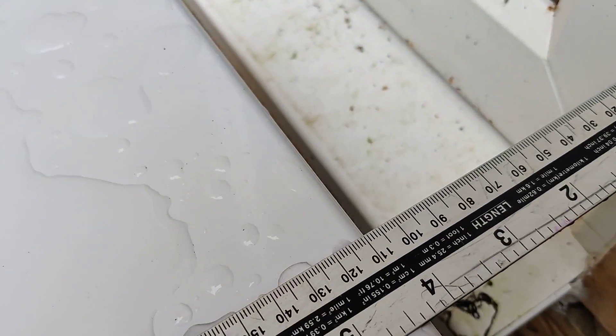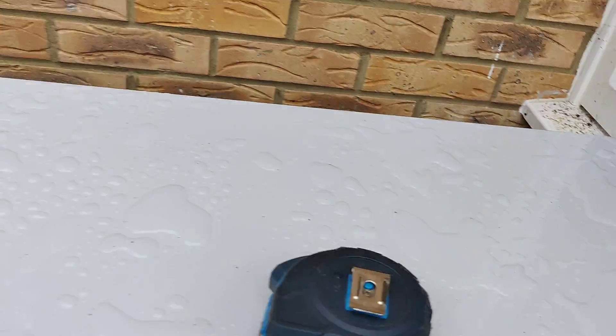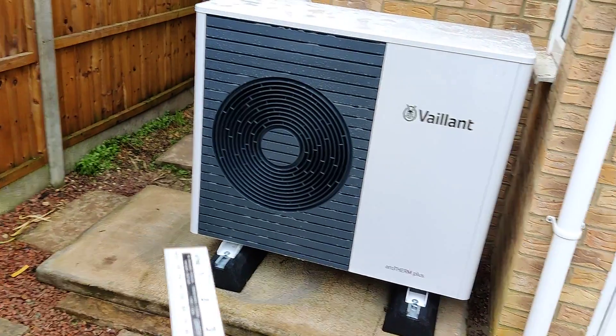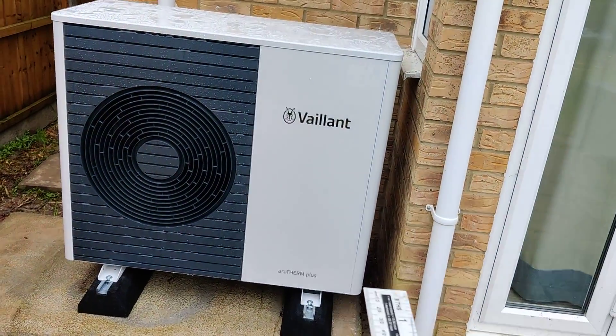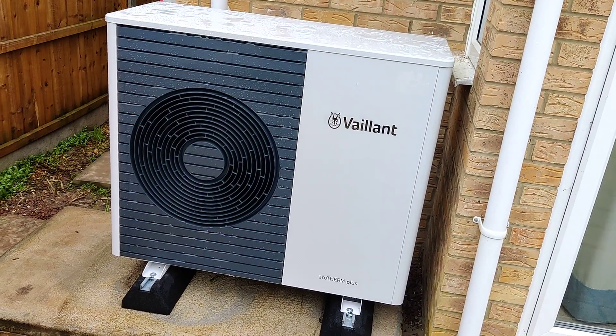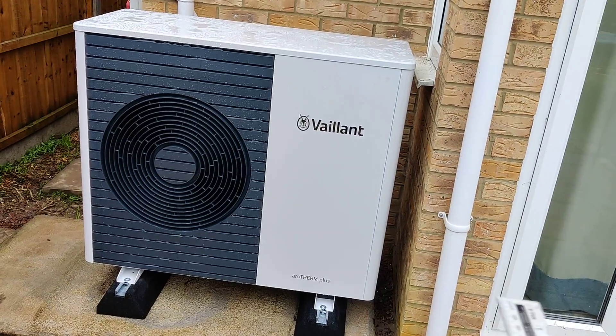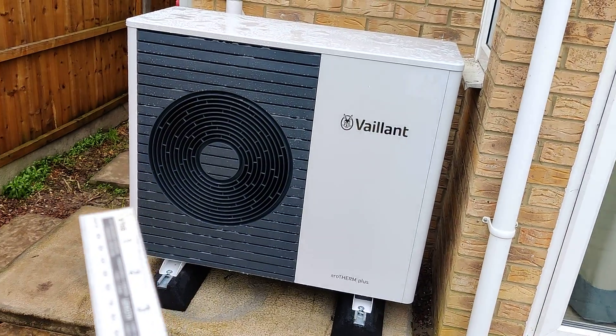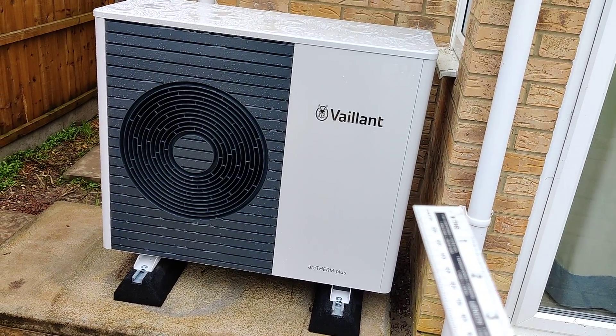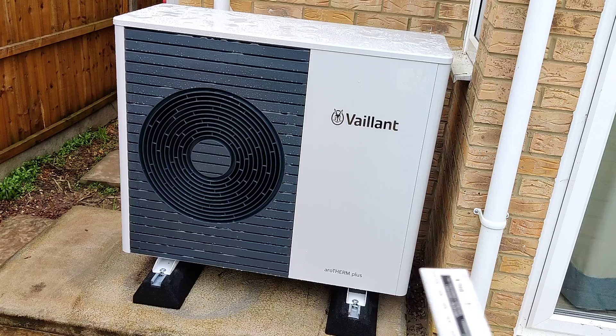Over this side where people said we didn't have clearance — we've got 110mm. Vaillant say they want 100mm on the left-hand side and 500mm on the right-hand side. This isn't for airflow reasons — I did contact Vaillant and asked them specifically why they want 500mm on the right and only 100mm on the left, and their reasoning was service access.